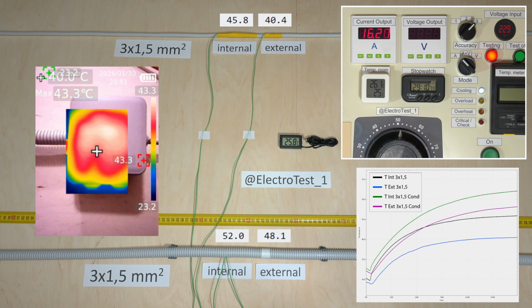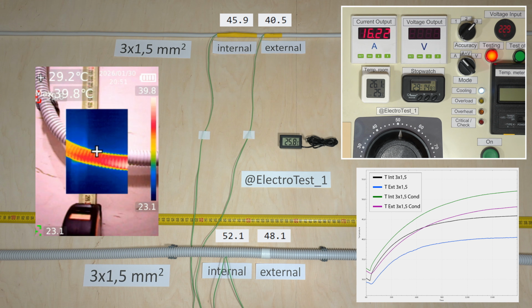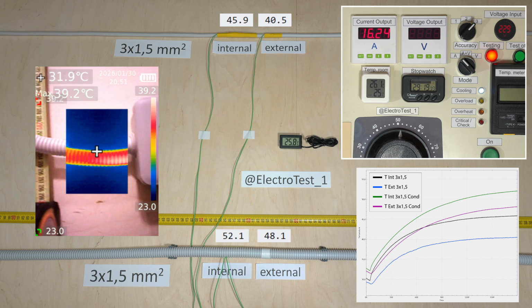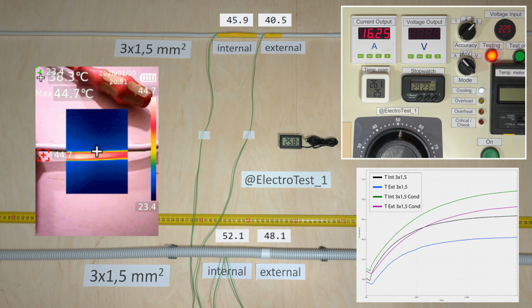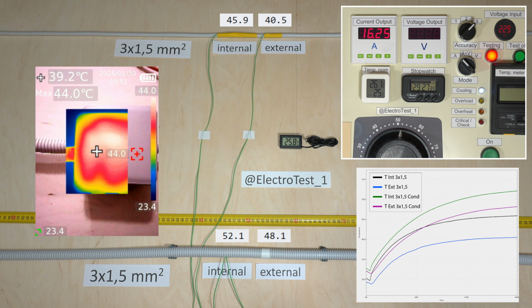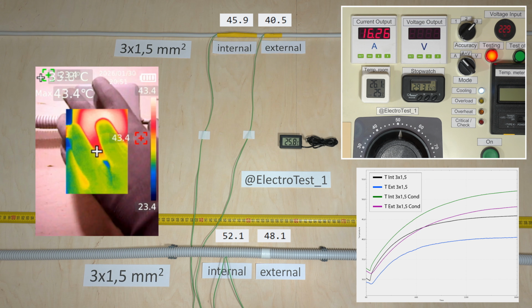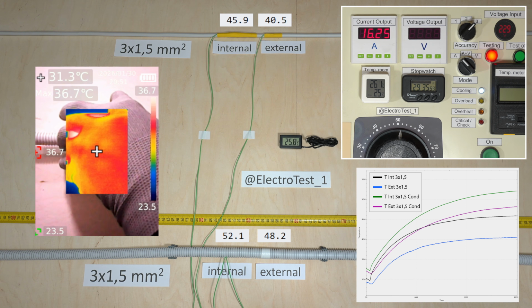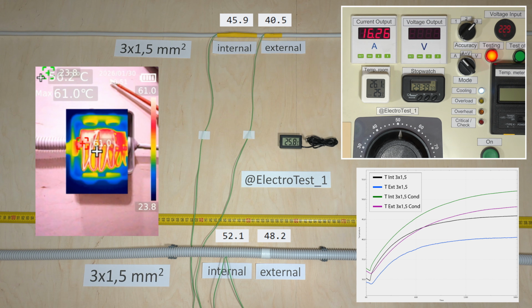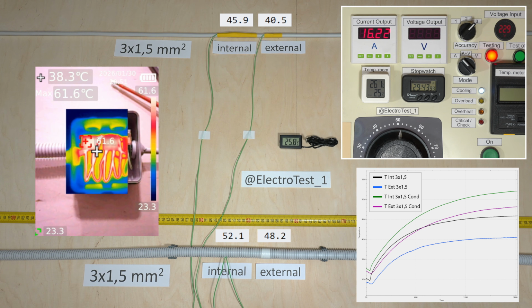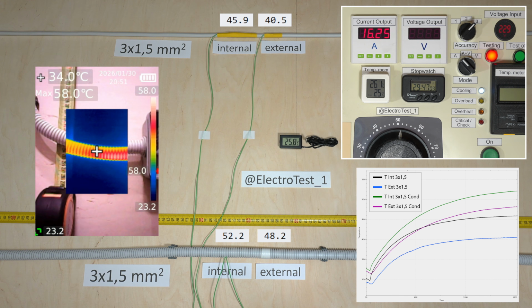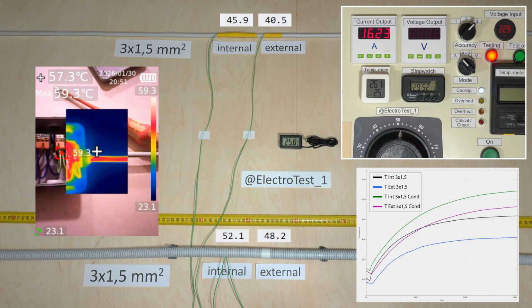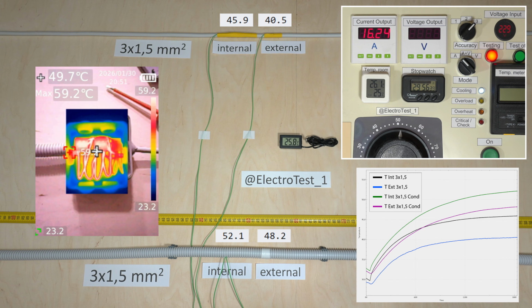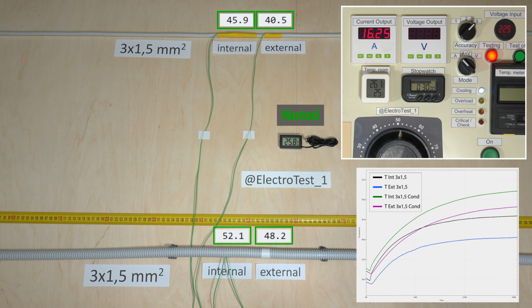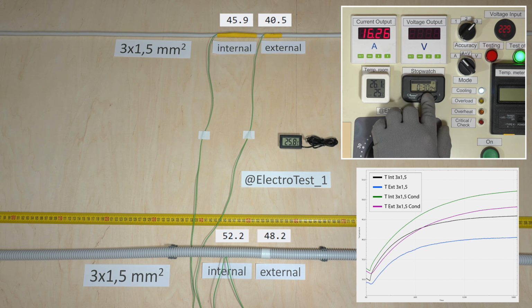The outside of the box is about 40 degrees Celsius. Inside, it is already 61 degrees Celsius. Internal cable temperatures: without conduit 46 degrees Celsius and inside the conduit 52 degrees Celsius. Therefore, the insulation is warmer as well.